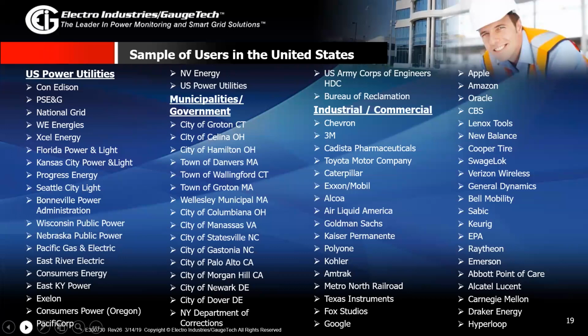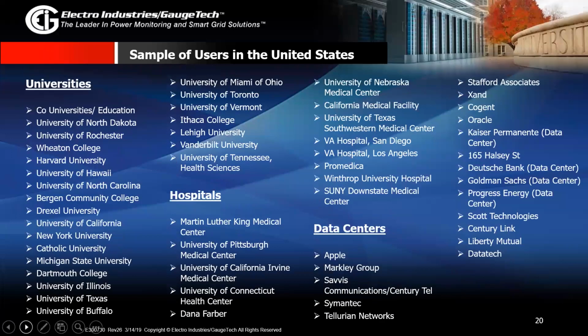There are other universities, hospitals, and data centers that will use high quality power quality meters on their mains, so that they're making sure they don't have harmonics, they don't have voltage sags and surges, because if they do have issues on their main lines, that can trickle down to their equipment, and then that can actually burn out their equipment or reduce the overall efficiency of the facility that they're running. Some samples of our international users, most of which are actually utilities all over the world.